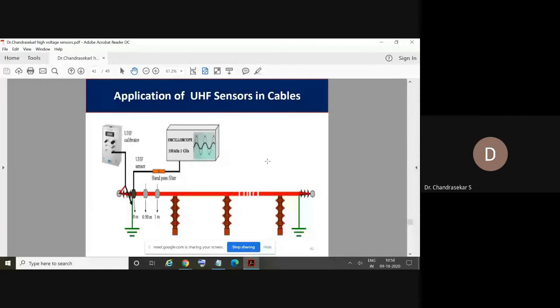So that's what I have told, that even in a big size transformer, they are creating an artificial fault in one particular phase of the winding, and they are able to exactly locate in the three-dimensional view where the fault is, using these UHF sensors. In such a way, the technology is developed now. So even in big size transformers or any equipment, you can easily monitor or locate where the fault is. That is the biggest advantage of these acoustic sensors and these UHF sensors.